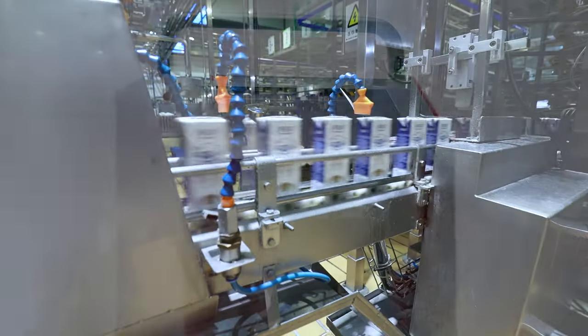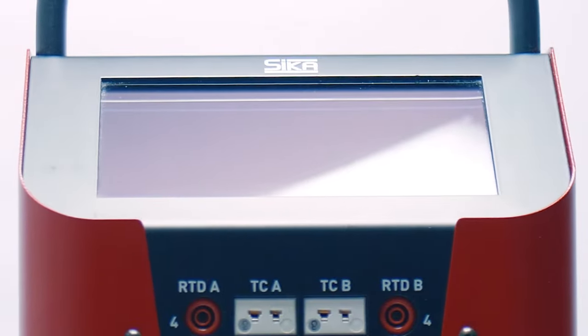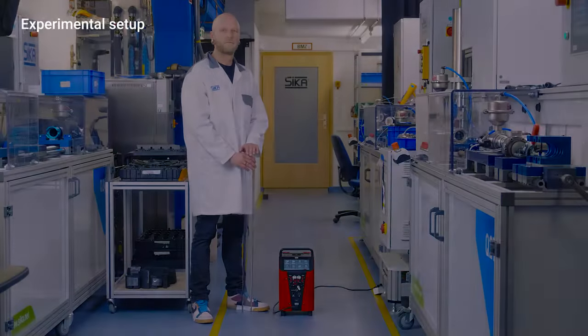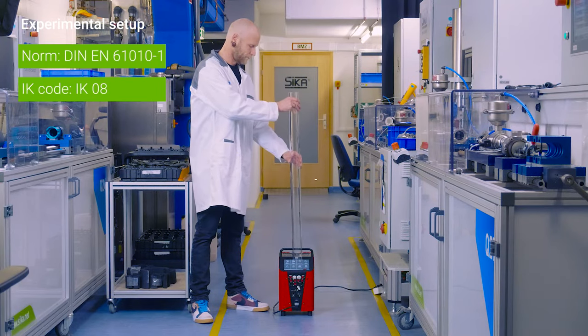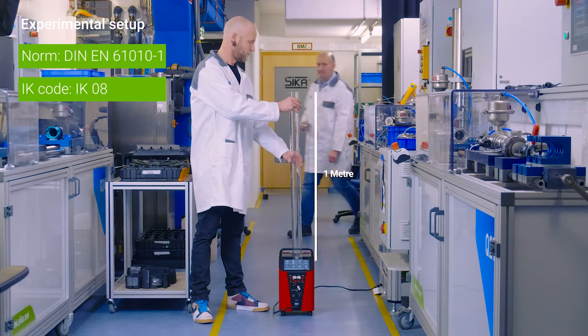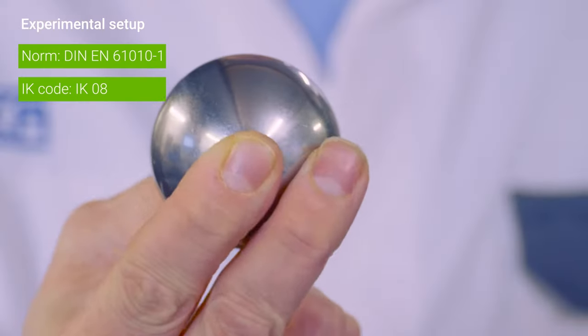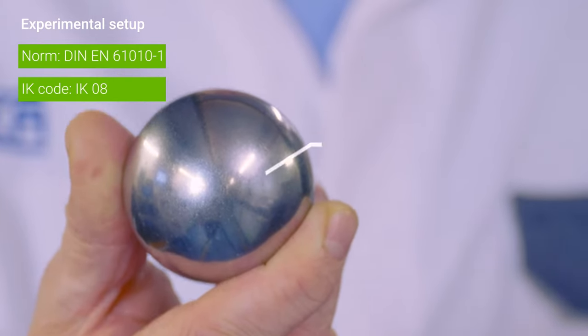We are aware of this danger and have therefore manufactured our touch screen using exceptionally strong safety glass. In doing so, we employed the DIN EN 61010-1 standard, which states that a ball weighing 500 grams must not cause any breakage when falling onto the glass from a height of 1 meter. This corresponds to the IK code IK08.